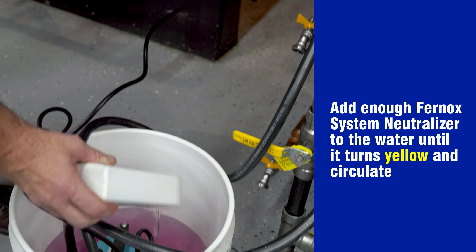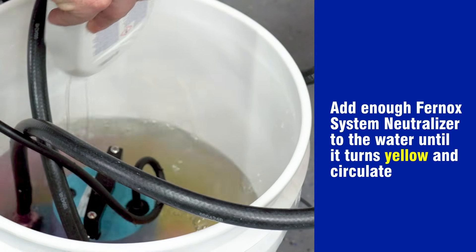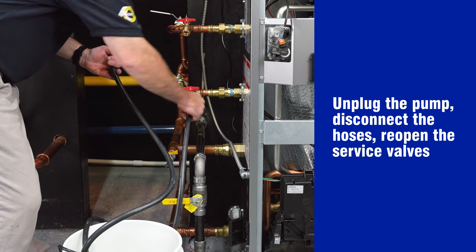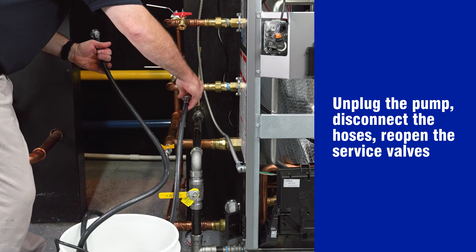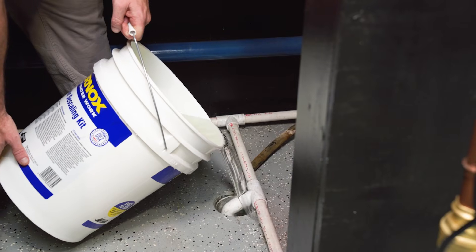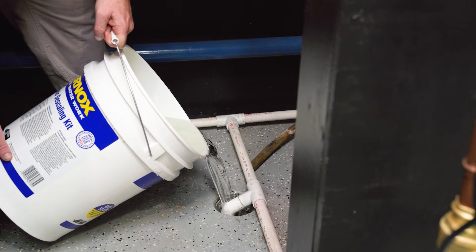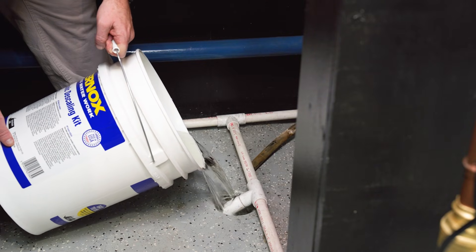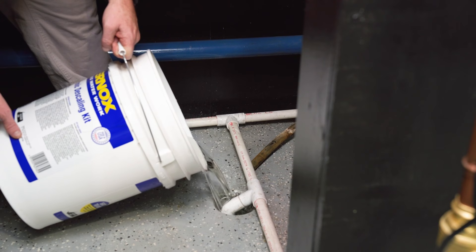Add enough Fernox system neutralizer to the water until it turns yellow and circulate. Unplug the pump, disconnect the hoses and reopen the service valves. The yellow fluid can now be disposed of using any available drain, including those drains that may be attached to a sewer or septic system in accordance with local and national regulations.